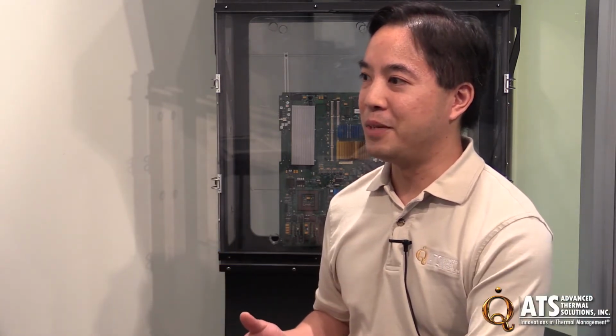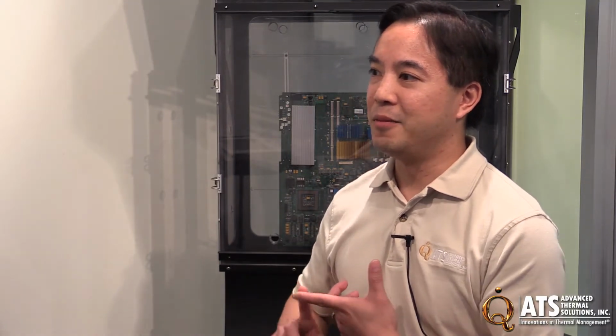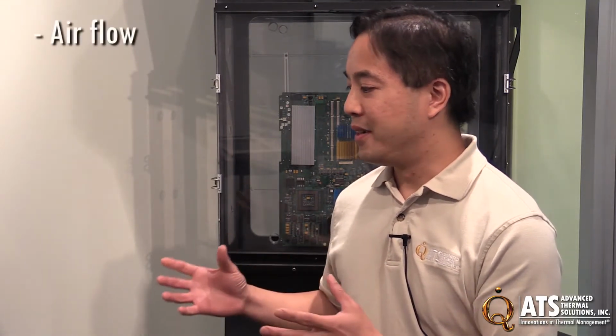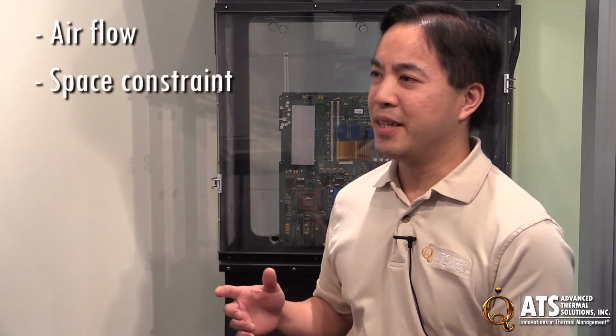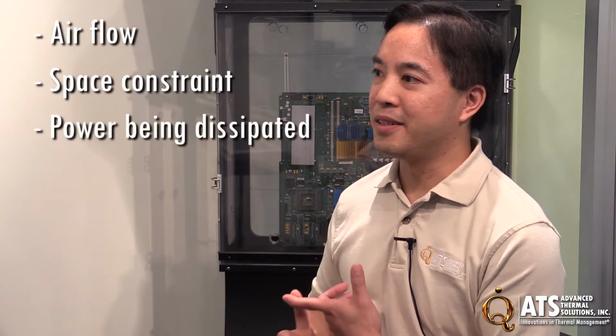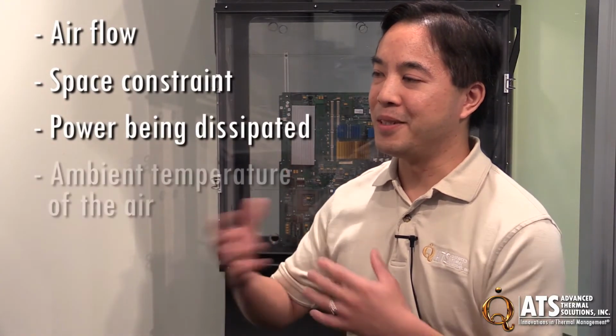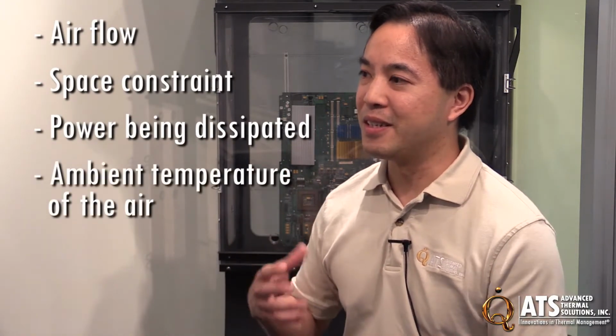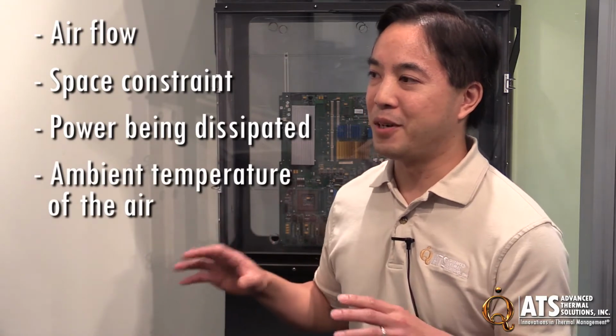We usually start with a few basic parameters. We call them boundary conditions. So we start with a few boundary conditions, basics like how much airflow we have, how much space constraint we have around the heatsink, and how much power we're dissipating, as well as the ambient temperature of the air coming into the heatsink. So those are the real basic parts that we need to start out with.